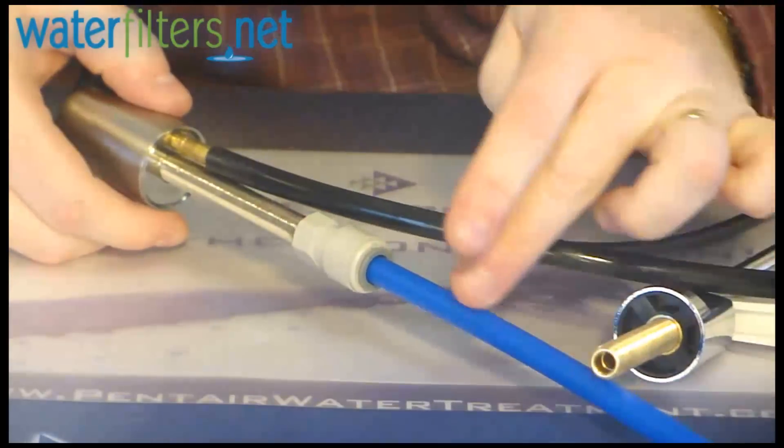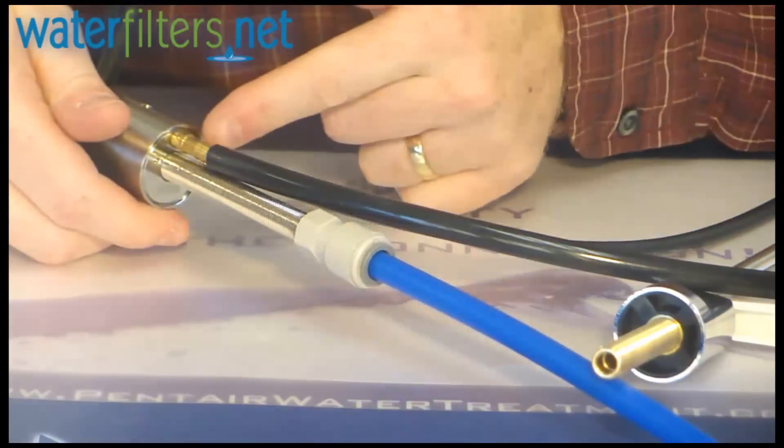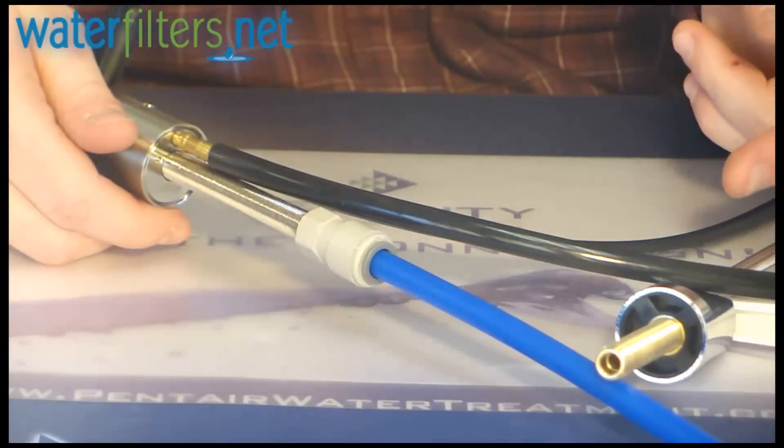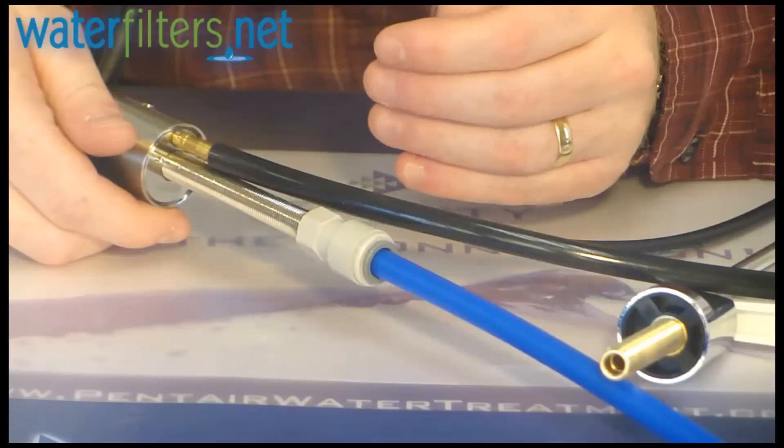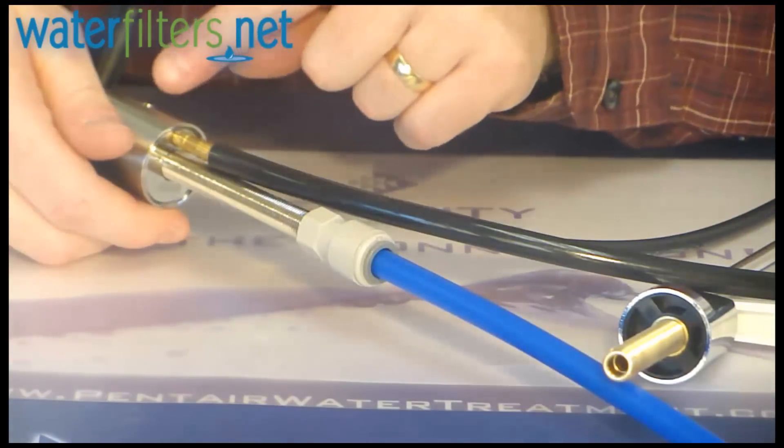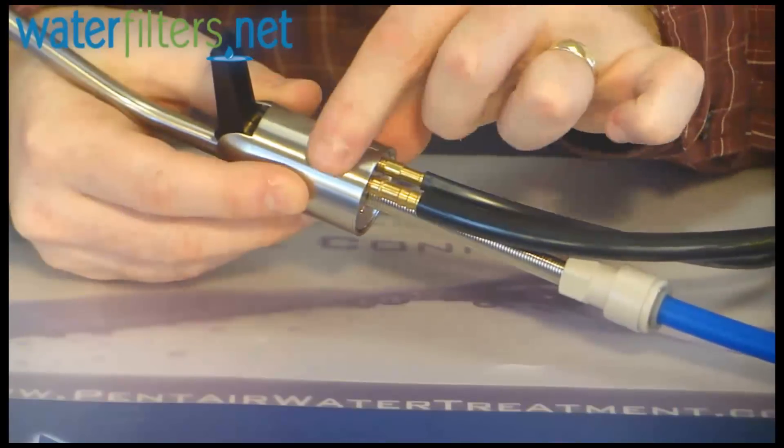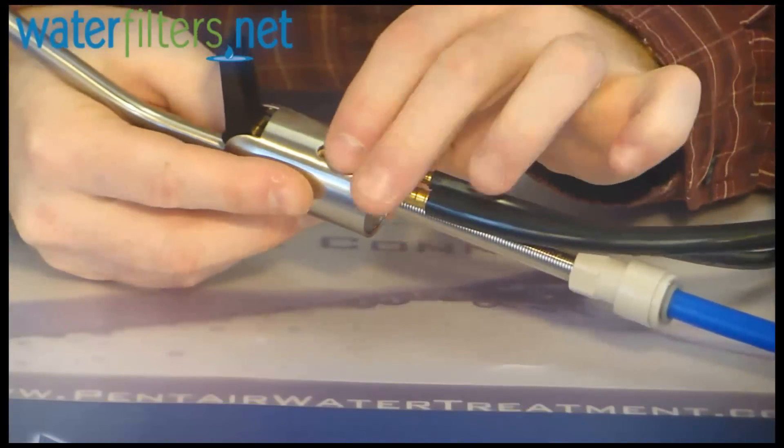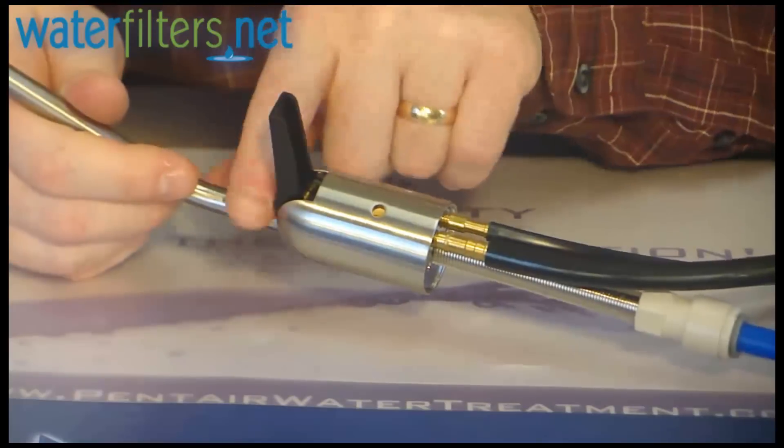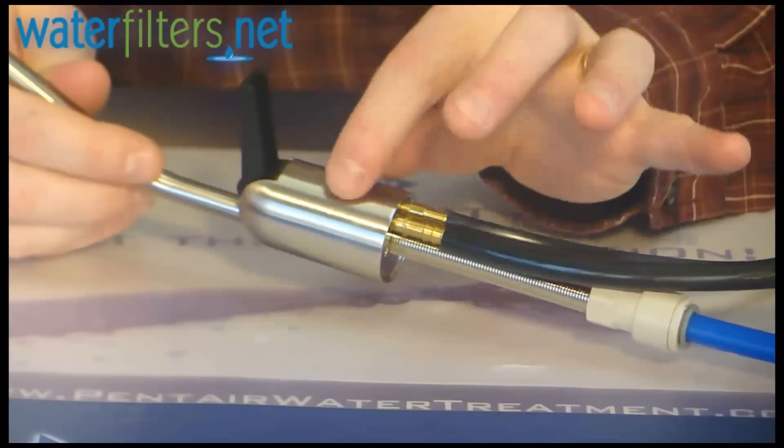So you have good water in to the threaded stem, and then you have drain water in and drain water out to the actual drain. Then if there's reverse suction, you won't suck crud out of your drain. You'll suck air from—you can see here there's a weep hole on this faucet. On some of them the weep hole is on top, in back, behind—it can be in any location, but it's an air gap to suck air if there's reverse suction.